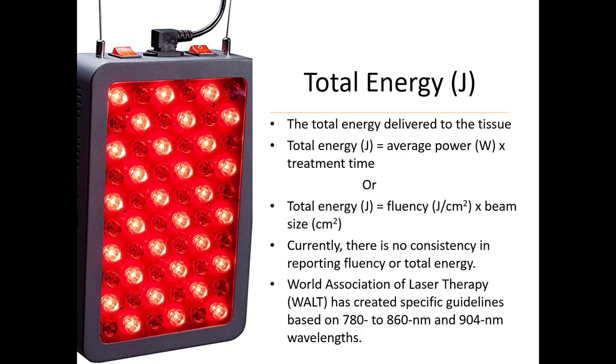The total energy in joules. The total energy is delivered to the tissue. This is a calculation of the total energy in joules, which is calculated from the average power in watts times the treatment time in seconds.